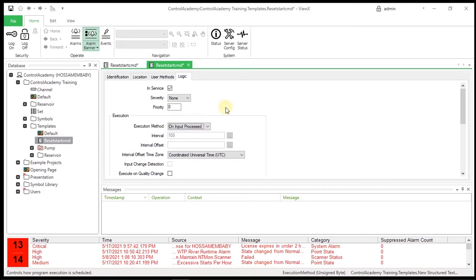The start point is referenced as a read/write variable in the logic program and is both read from and written to in the program. If the start point was also used as a trigger for this program, the execution would trigger from the start point, possibly update the start point which triggers the program again, causing the program to enter an infinite loop. For this reason, variables that are being read from and written to are excluded from OnInputProcessed calculations.